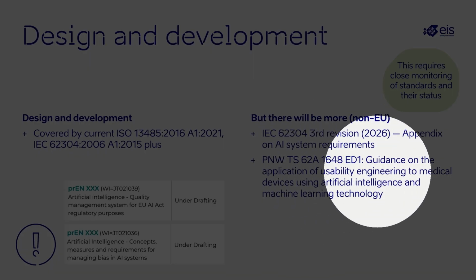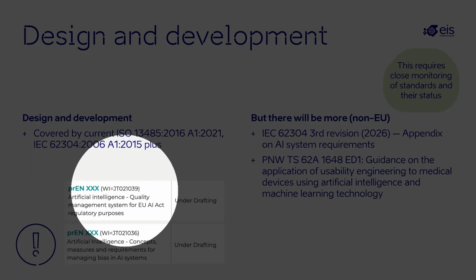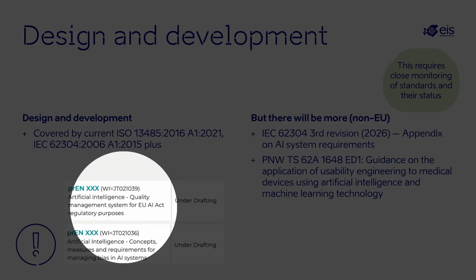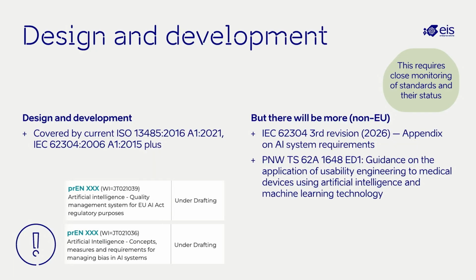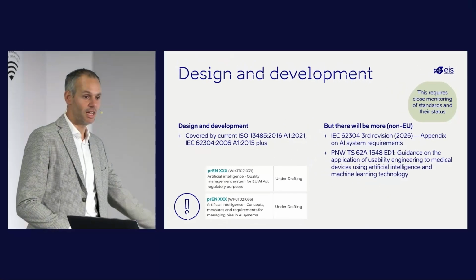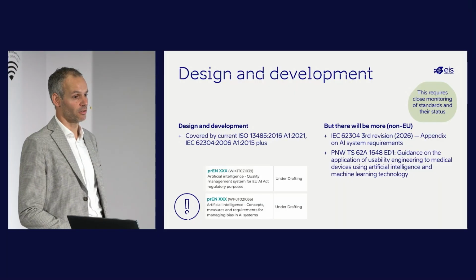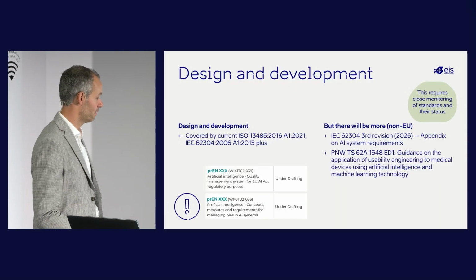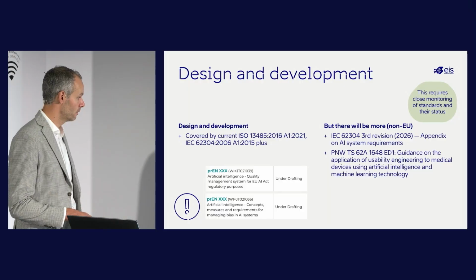There's one on usability engineering that's under development, specific to AI systems. And then you see on the EU level, and I think this is one of the most important standards for medical devices and AI systems, there's going to be an additional quality management system standard. So we'll have the ISO 13485, and we'll have this one. And for those who are aware, there's already an international standard, the ISO 42001, which might be accepted outside of the EU by some of the regulatory authorities. So again, three quality management system standards, and to me, it's a mess.